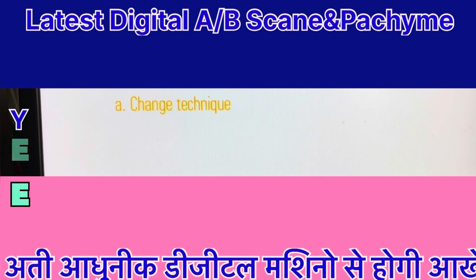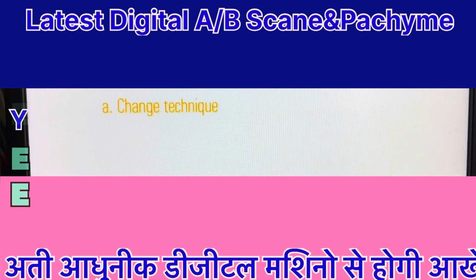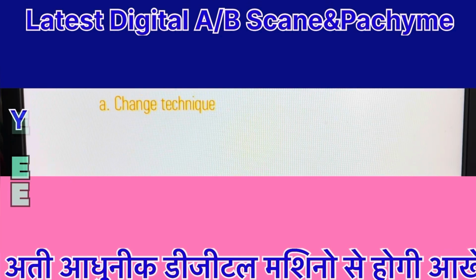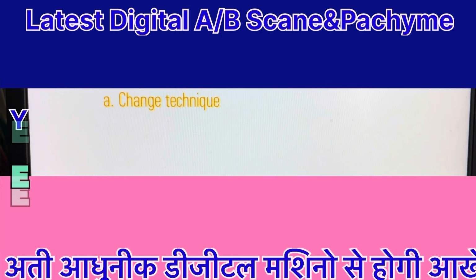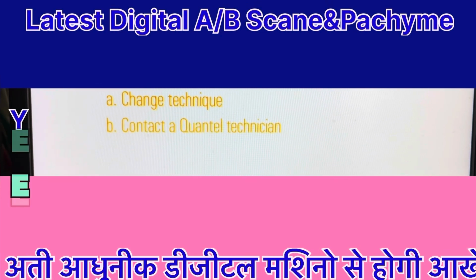4. I'm not getting an ultrasound signal, but my fixation light is fine. Can I try to fix this without calling a Quantel technician? Turn off the system, unplug the probe, and check the probe connector cable to ensure the two pins are straight, not bent, and in good condition.